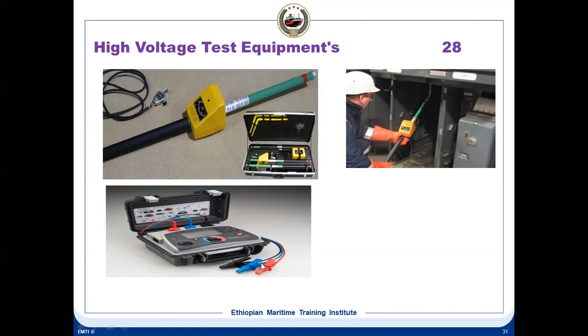It is connected on the outer part. Remember, this is a guard terminal. This megger can also measure insulation resistance, and PI, that is the polarization index test. By selecting the PI switch, you can measure the polarization index also. So this is a high voltage megger.